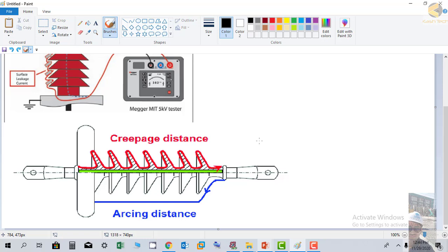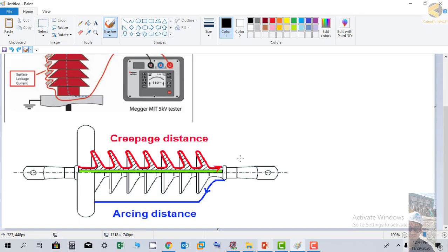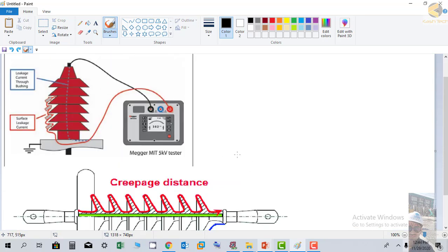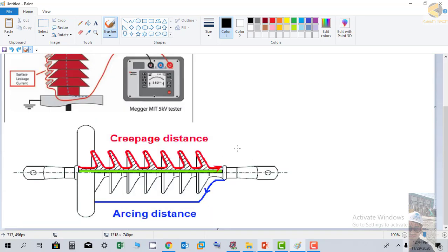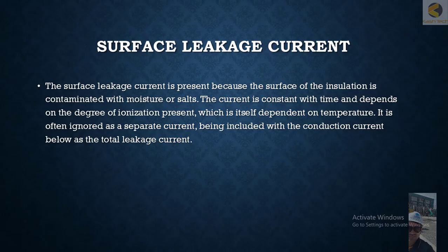To eliminate surface leakage current, equipment is normally provided with a guard terminal. You can connect this to the insulator surface, and it will eliminate the surface leakage current to get proper readings. Thank you very much, we'll move to the next topic.